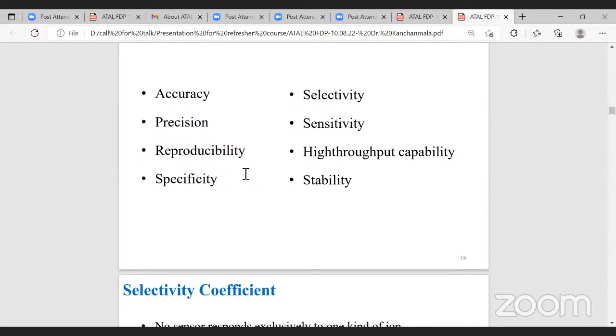Now, one of the major features of a sensor is the selectivity coefficient. I told you that it is very difficult to develop a sensor which is highly specific. So a sensor will tend to give a response to two analytes maybe. Take an example, the glass electrode, which is very common to measure pH, commonly known as the pH combined electrode. This combined electrode, which is used to measure pH, not only gives a response to pH or H+ ion concentration in the water, it also responds to the Na+ ion. So you wanted to determine H+ ion concentration, but your sensor is also responding to Na+ ion concentration.